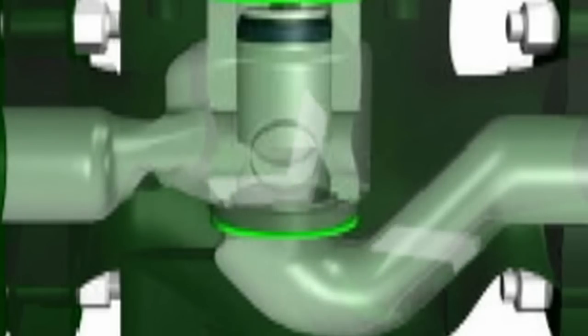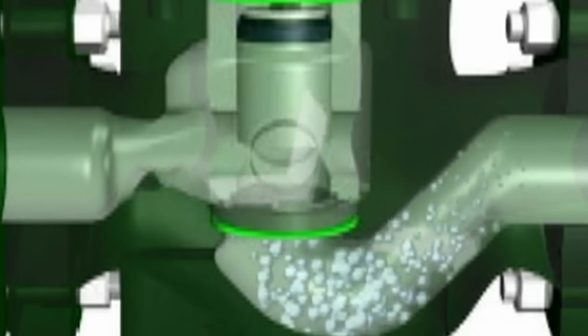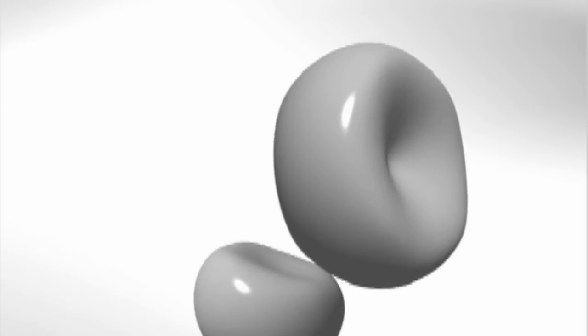When there's not enough pressure on the inlet side of the pump, cavitation may occur. This leads to part of the liquid turning to vapor inside the pump. When the pressure increases, the vapor is then compressed back into a liquid. This can create pressure shock waves of up to 10,000 psi, resulting in significant damage to pump components.